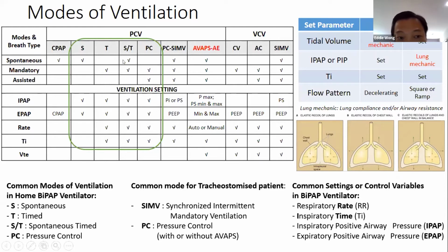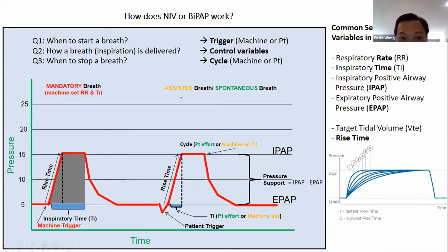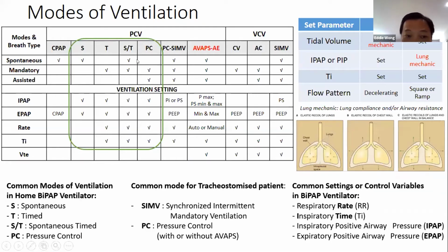So what is the difference between the spontaneous breath type and the assisted breath type? Both are triggered by the patient. The patient must have the effort to trigger. Only then will the machine raise the pressure to inflate the lung and deliver the air to fill up the lungs. But when it comes to when to stop, to cycle a breath, the assisted breath will follow the I time setting. The spontaneous breath type will follow the patient's effort. The patient decides when to stop the breathing based on their own efforts. That's why, if I go back to the previous slide, you see S mode is spontaneous, here is assisted.